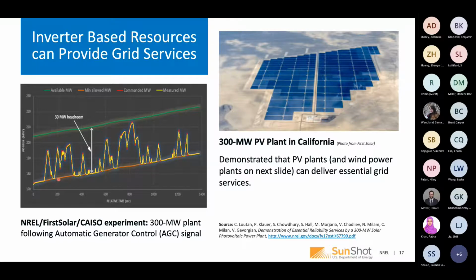Typically, the large-scale coal plants, gas plants, et cetera, do this type of fast regulation service for the system operator, and PV plants and wind plants have not been required to do this. But what we wanted to demonstrate is that these inverter technologies actually have this capability. And not only that, they respond extremely well to commanded signals. So in the future, as we look for wind and solar to play an ever-increasing role in the grid, they will have to provide these essential grid reliability services to maintain stable operations at high levels of inverter-based resources.